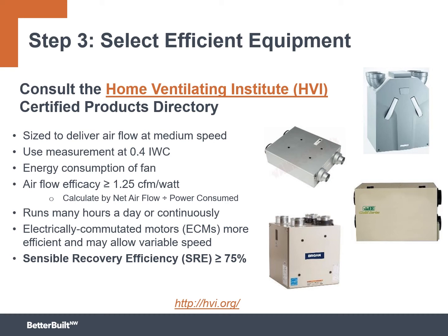And then finally, while yes, there is a level in both the Oregon and Washington codes that allows for a 0.65 or 0.66 SRE piece of equipment, if you want to maximize that tempering of incoming air and get the best overall efficiency, we really want to look at a sensible recovery efficiency, or SRE, of 75% or higher. Again, you can find all this on hvi.org.